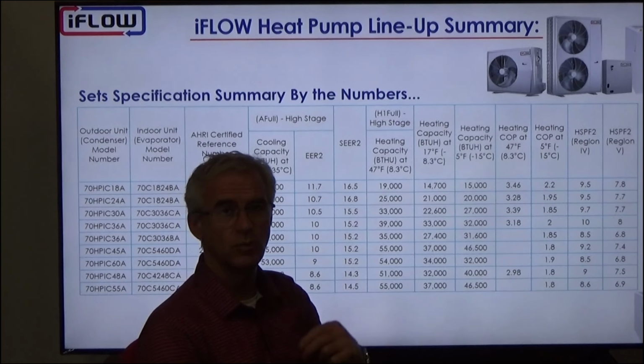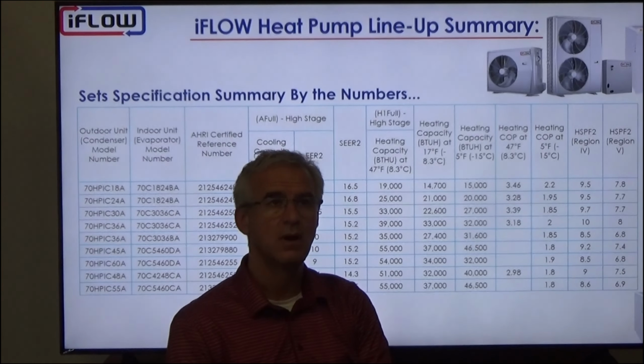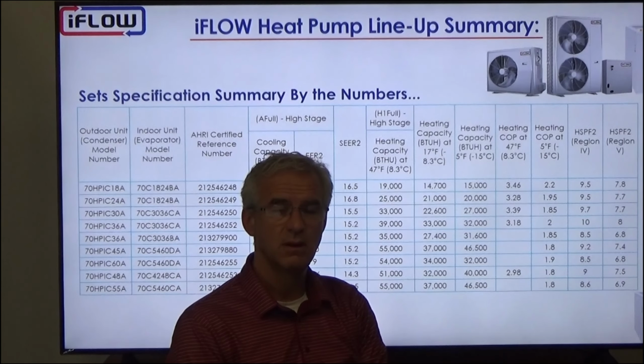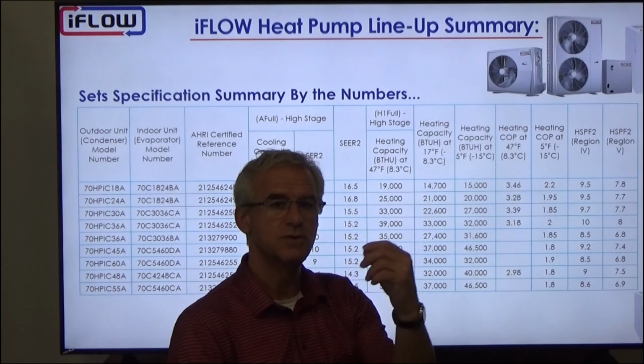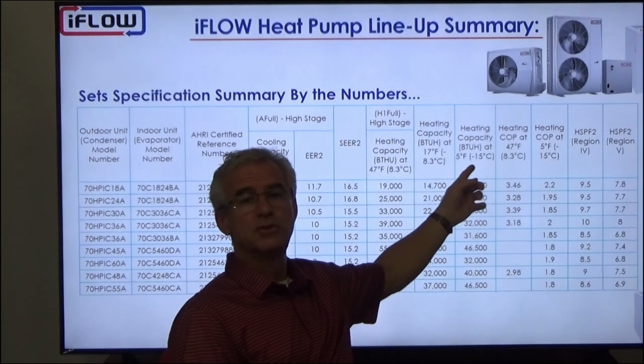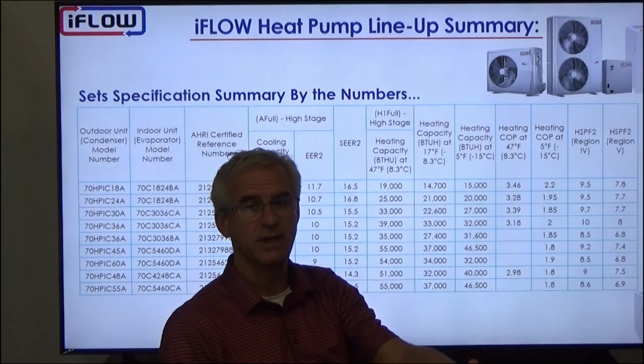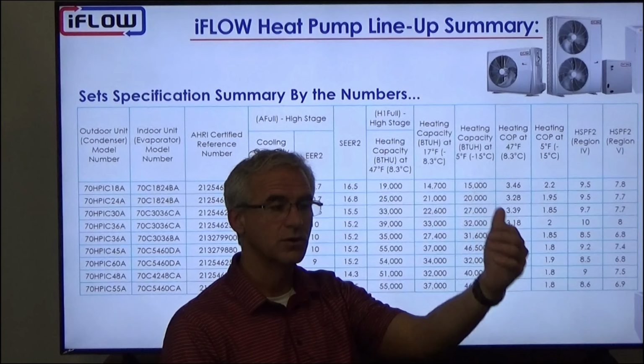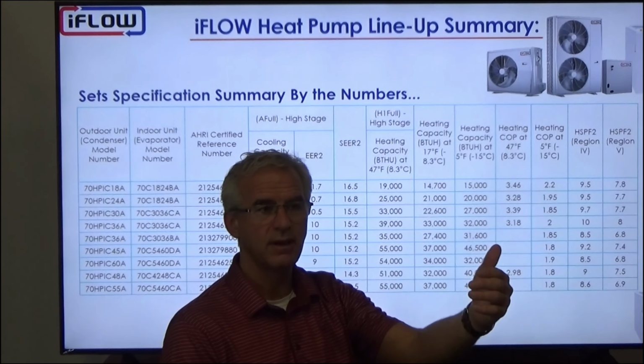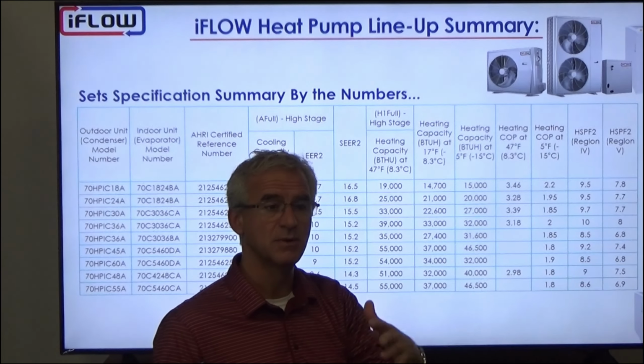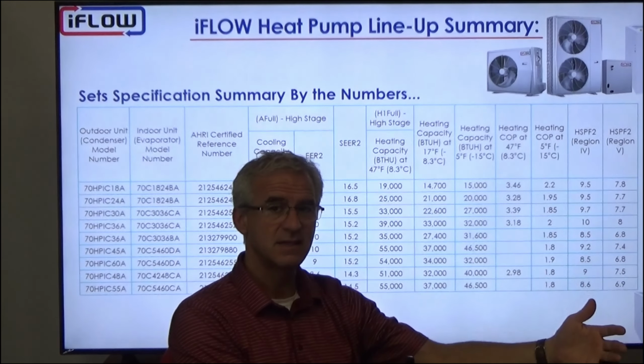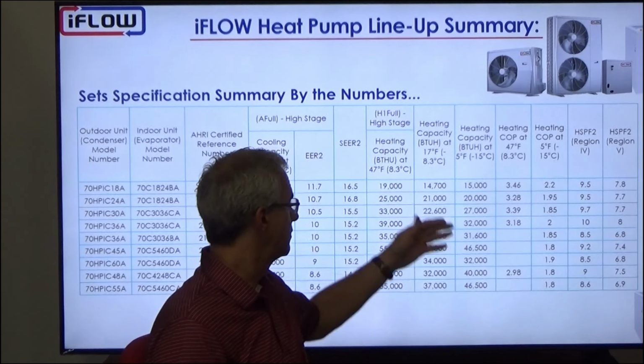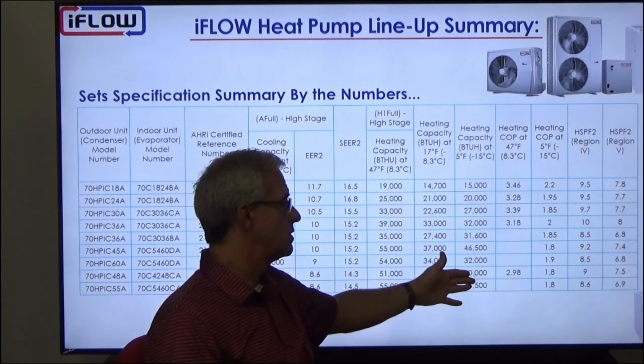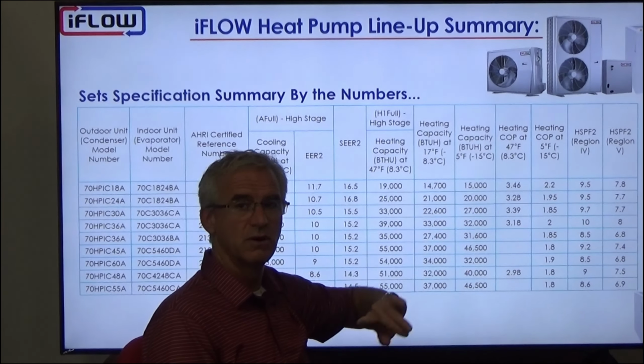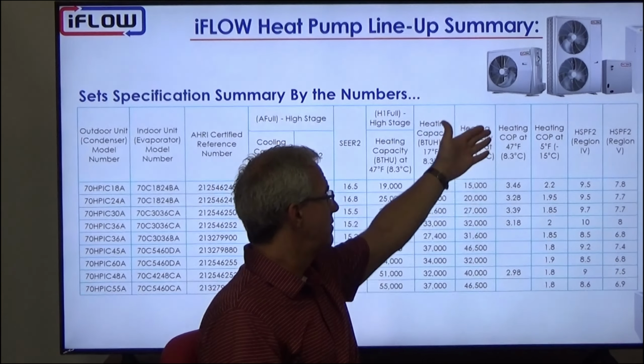We have to look at that when we're sizing systems to make sure we are able to deliver the BTUs you need at the outdoor temperature in your area, right? So we look at the coldest winter design in January and February. If we're expecting the heat pump to be able to deliver full capacity, we have to look at the numbers at that temperature and make sure we're able to meet your heating load. We have the COPs.